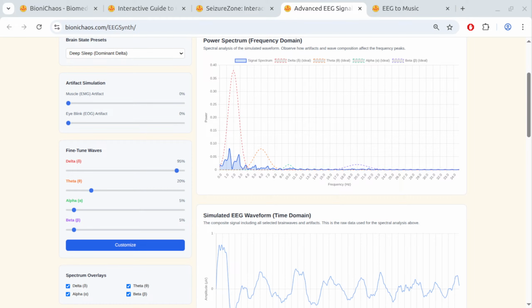And then there's everything else, the whole world trying to butt in. Precisely. That's the non-physiological stuff. It can be mundane things like a bad connection where the electrode meets the scalp, maybe it's placed wrong, or faulty wiring. It's technical glitches. Right. But it also includes electromagnetic fields just floating around in the environment. The hum from the power grid, 50 hertz here, 60 hertz in the US. The mains hum. Other medical equipment, if you're in a hospital, your cell phone, even fluorescent lights, all that can interfere. Sometimes you see what's called an electrode pop. A pop? Yeah, it's like this abrupt, spiky jump in the signal when an electrode just momentarily loses good contact. It really underscores there's a constant battle researchers fight just to get a clean recording.